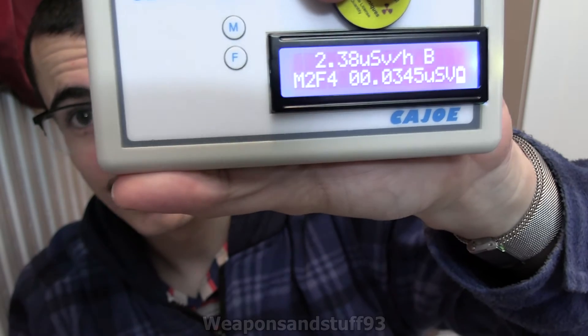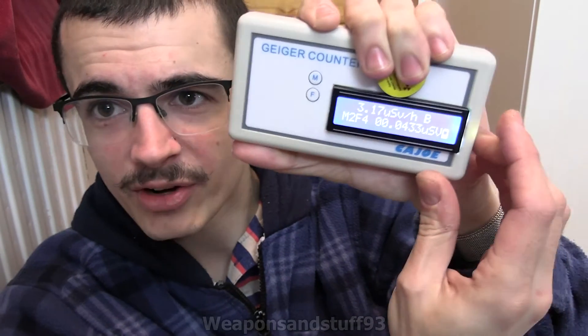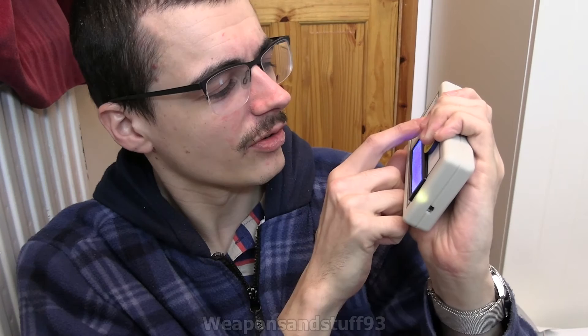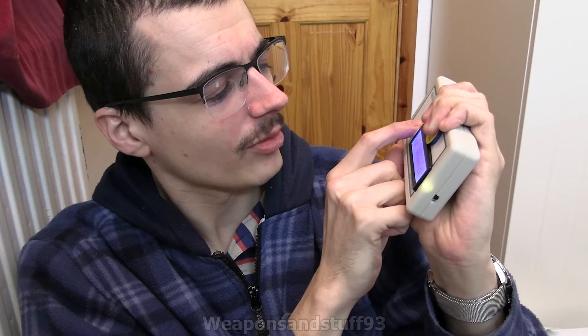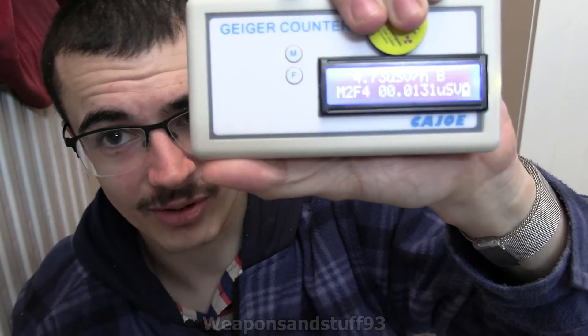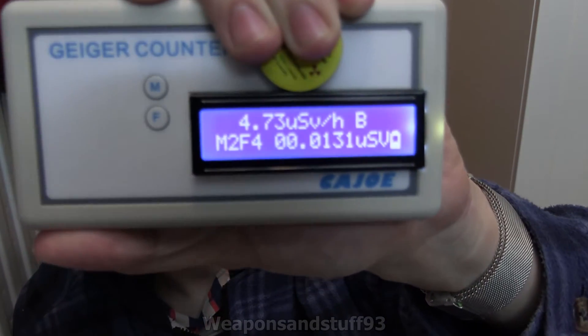One thing I want to test — if you turn this off and on, I'm pretty sure the only annoying thing is it wipes the dosimeter; it has no memory for it. Yeah, it does wipe it if you turn it off and on. So that's the only annoying thing — if you turned it off and on, you wouldn't know how much dose you've accumulated. It's not like the Soeks in that regard.